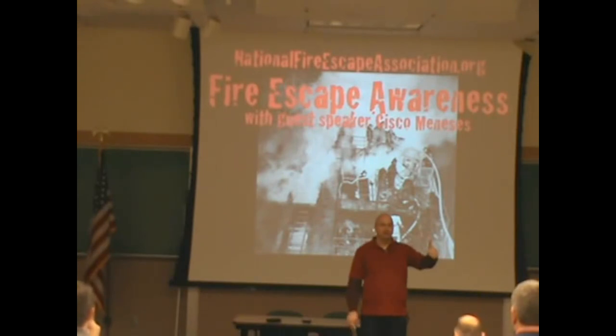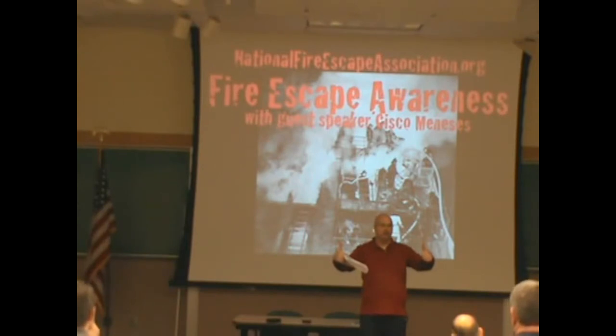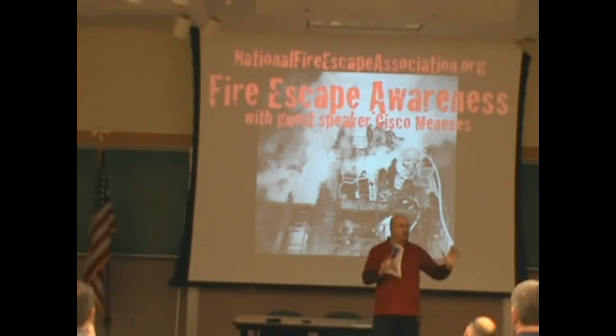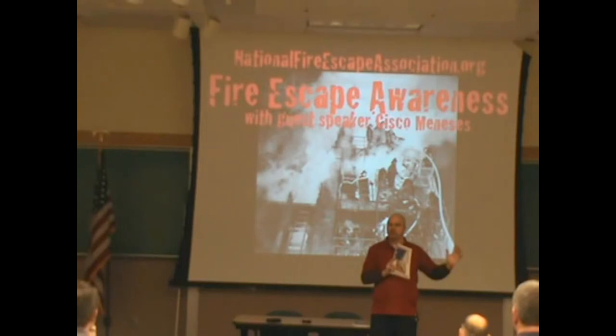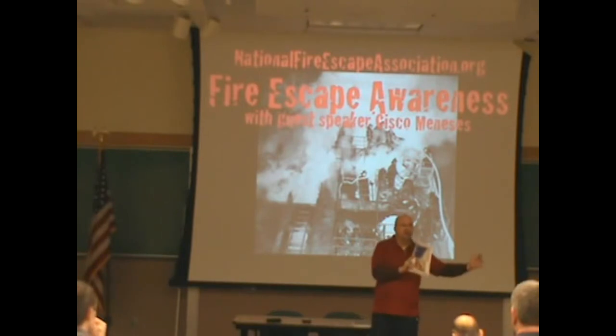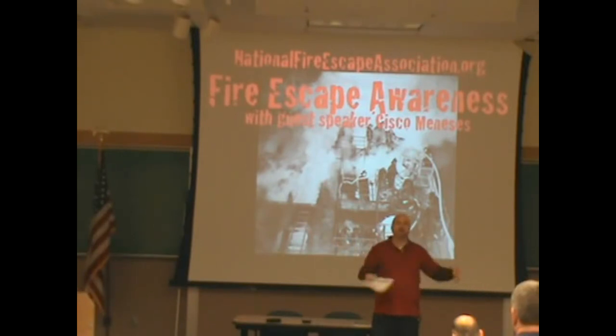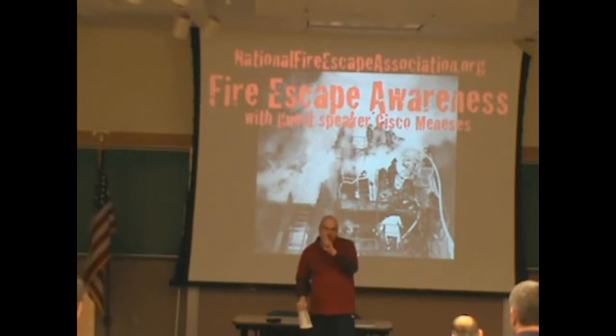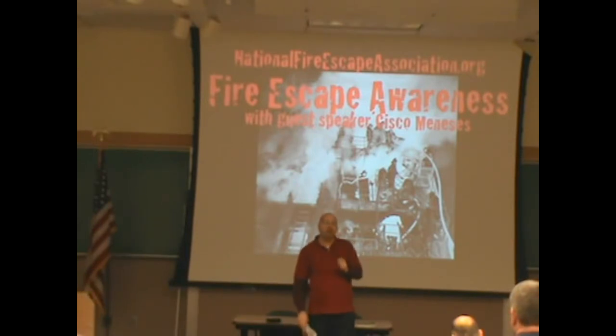We're really going to discuss the whole class on other evidence of strength. Does a load test give you assurance? It gives you a piece of paper. Other evidence of strength currently has two categories. The norm — 90% of the time — is an opinion letter. We're going to flip that. If you spot repair a fire escape as other evidence of strength and leave behind original hardware, I'll order a load test. If you fully refurbish it, I won't make you do a load test. Even in other evidence of strength, someone's going to try to jam an opinion letter down your throat — 'I've got 30 years experience, my firm has 75 people.' Good. You and your employees can go walk up the fire escape. No — just order the load test.